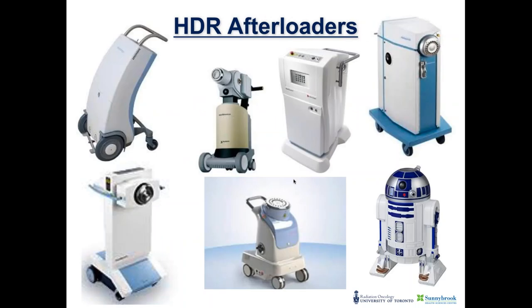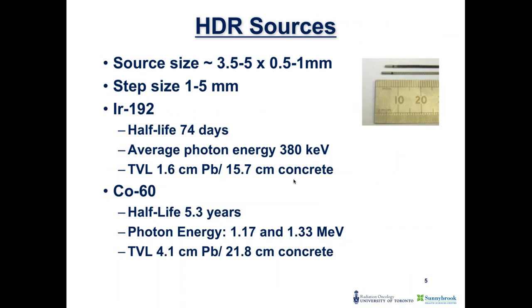The big advantage of HDR over LDR is that planning is completed after the applicators and catheters are in place. Afterloaders come in different sizes and shapes, but they all house a high-activity radioactive source and have a cable that can be advanced remotely along the implanted catheters. The HDR source can be as small as 0.5 mm in diameter and 3.5 mm in length, with step sizes ranging from 1 to 5 mm depending on the equipment.